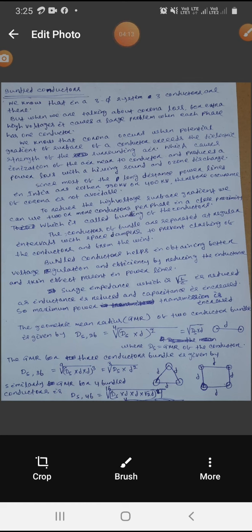From these discussions, we came to know that when we have to make extra high voltage lines, then obviously we should bundle the conductors for each and every phase of the transmission line. Now we are going to calculate the inductance of the bundled conductors. Before calculating the inductance, we should calculate the geometric mean radius, that is GMR, of the bundled conductors. Suppose each phase has two conductors.